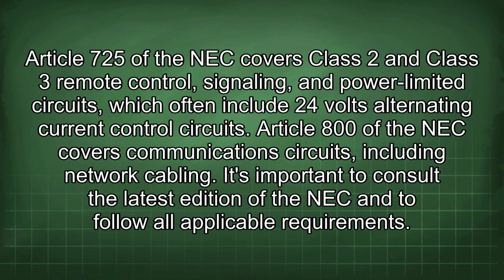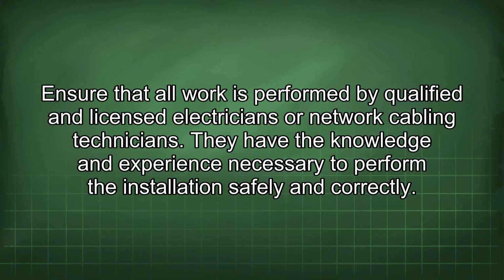Article 725 of the NEC covers Class 2 and Class 3 remote control, signaling, and power-limited circuits, which often include 24 volts alternating current control circuits. Article 800 of the NEC covers communication circuits, including network cabling. It's important to consult the latest edition of the NEC and to follow all applicable requirements. Ensure that all work is performed by qualified and licensed electricians or network cabling technicians. They have the knowledge and experience necessary to perform the installation safely and correctly.